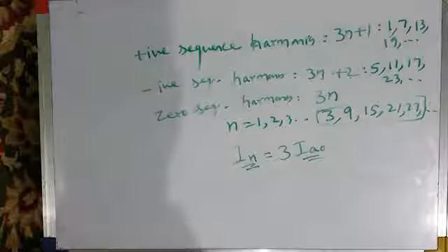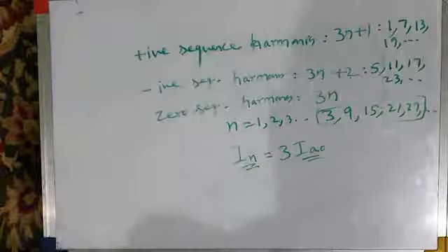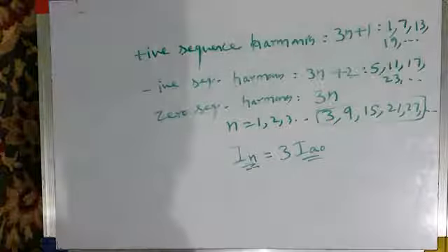And if your neutral conductor is thin, its cross section being smaller as compared to line conductors or phase conductors, it will cause neutral overheating and neutral burning. And to avoid that problem, the modern trend is to keep the neutral conductor as thick as line conductors.